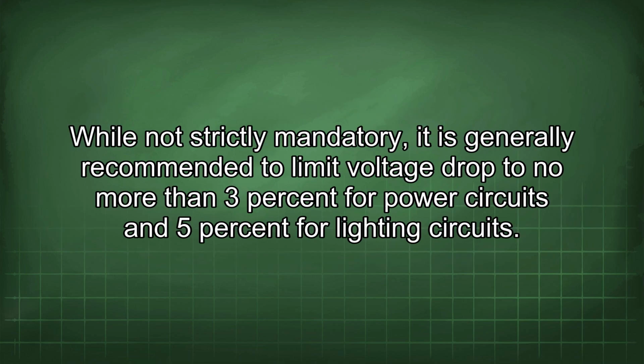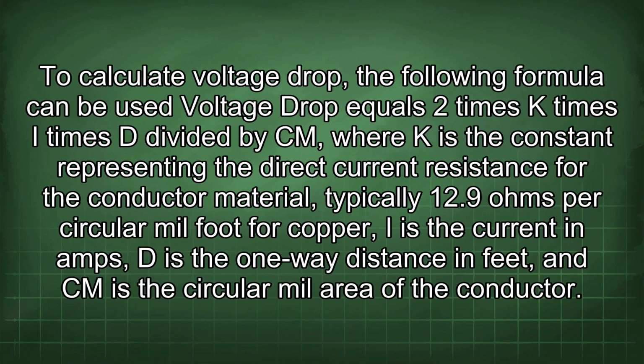While not strictly mandatory, it is generally recommended to limit voltage drop to no more than 3% for power circuits and 5% for lighting circuits. To calculate voltage drop, the following formula can be used. Voltage drop equals 2 times K times I times D divided by Cm, where K is the constant representing the direct current resistance for the conductor material, typically 12.9 ohms per circular mil-foot for copper.